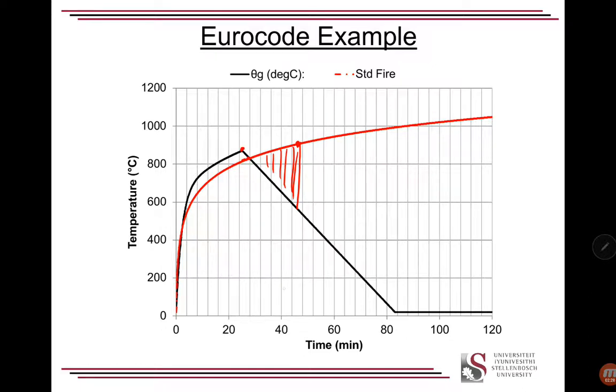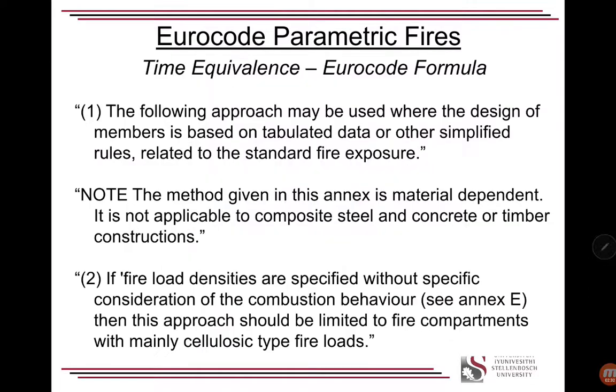Less than 25, 30 minutes, I mean, the parametric curve is above the standard curve the entire time until after about 27 minutes or so. Now, we're going to be using the Eurocode formula, the time equivalents in the EN 1991-1-2 code. And just some limitations to the equation we're going to be using are listed here based upon the annex.